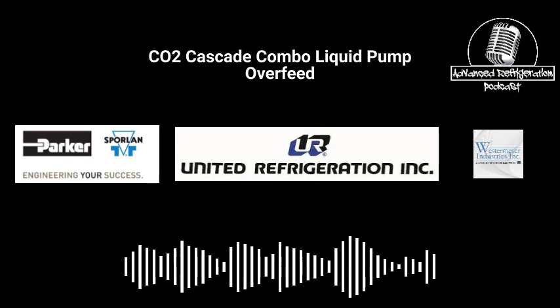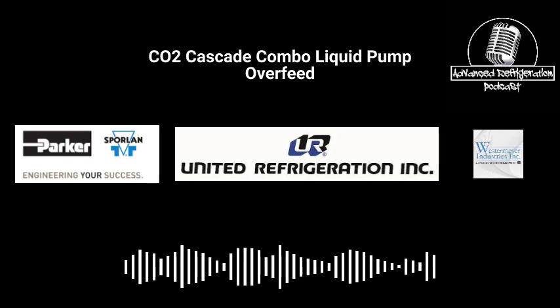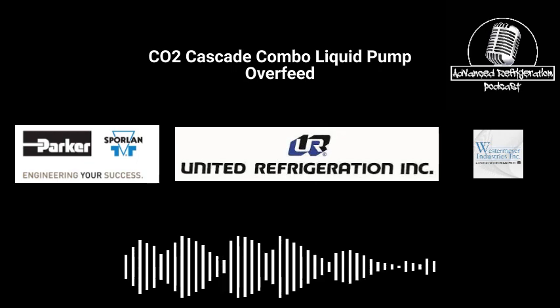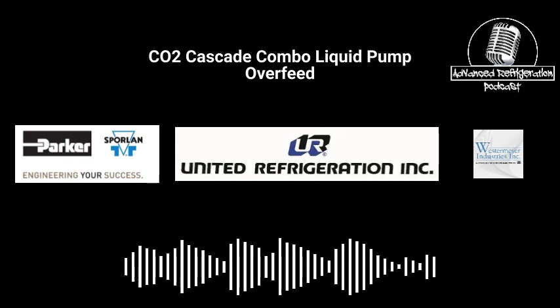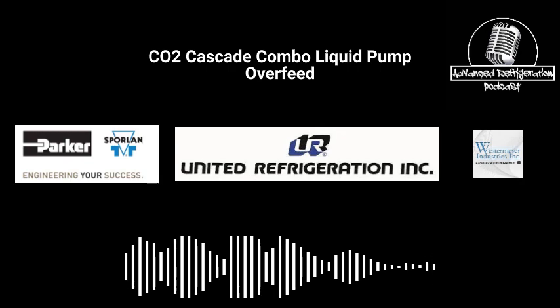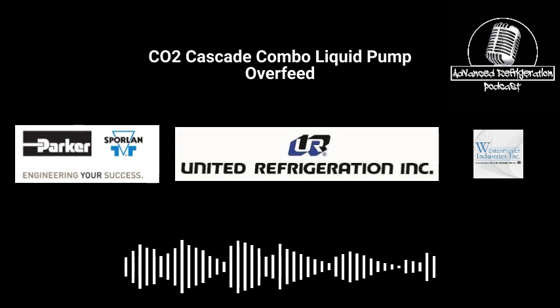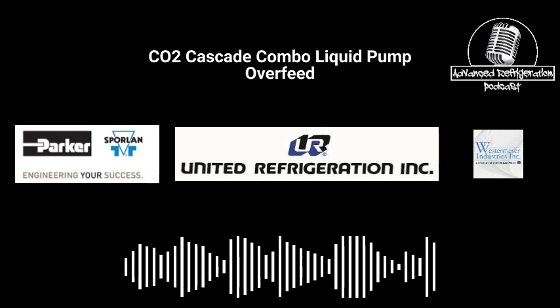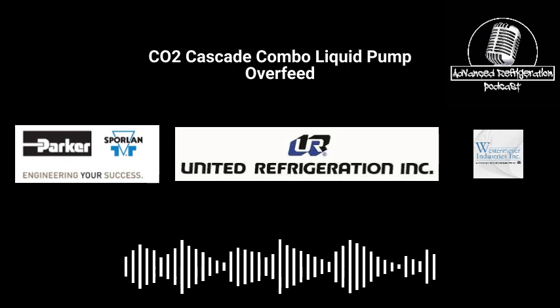So the high pressure settings on this rack: at 550 it's going to cut in, basically shutting down the rack, and at 490 it'll cut back out and let the rack run again. If it keeps going off on that high vessel pressure, usually something is wrong with one of the superheat controllers, a sensor being off, or a pressure transducer being off. You can also have non-condensables on the CO2 side, because then you have refrigerant going through, maybe flooding out, and causing the pressure to be higher. It's also going to be dependent on your suction pressure of your HFO, right? That's controlling the actual vessel pressure. And if you're not within tolerance, or you have a lot of movement there with unsteady pressures, that could be another deciding factor in whether this rack goes off on high vessel, because of those laggy pressures where you have the rack turning on, shutting off, turning on, shutting off.